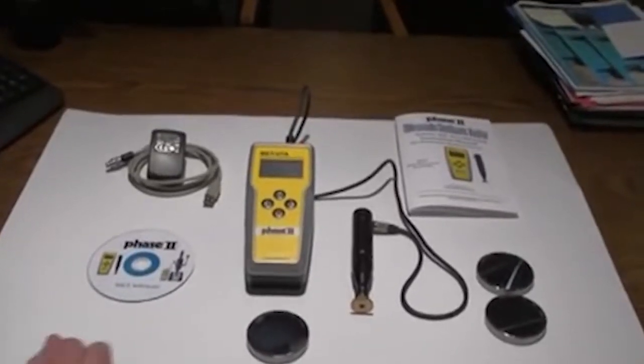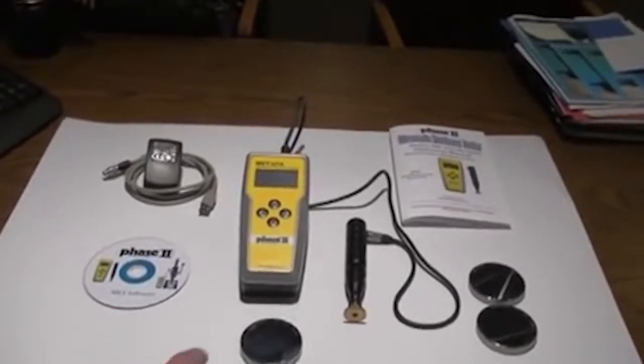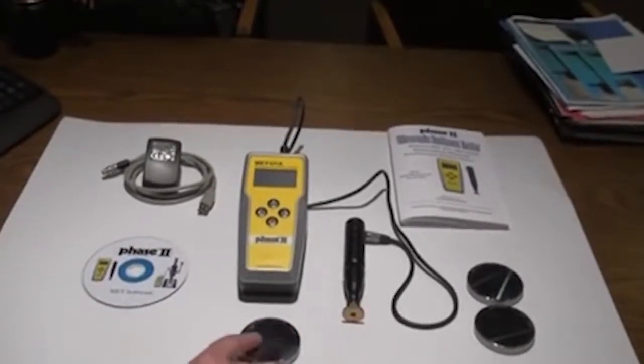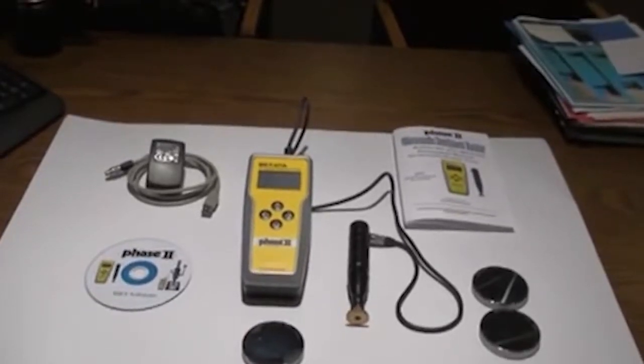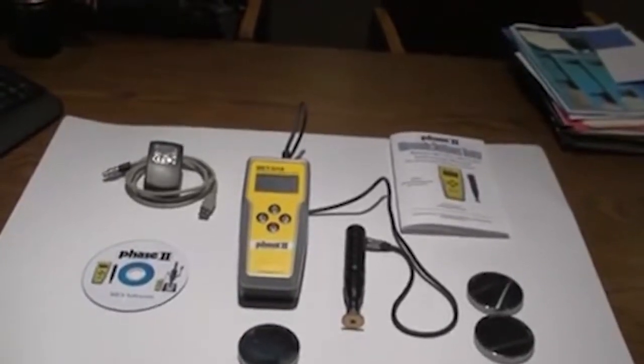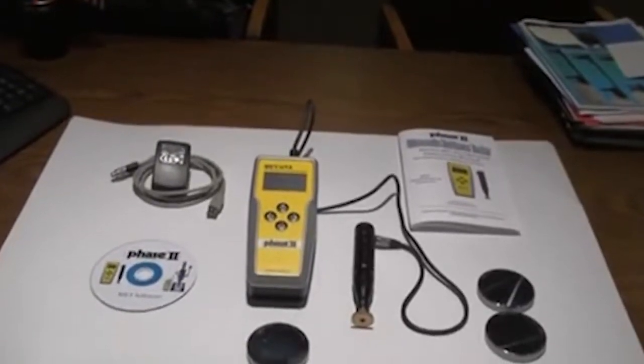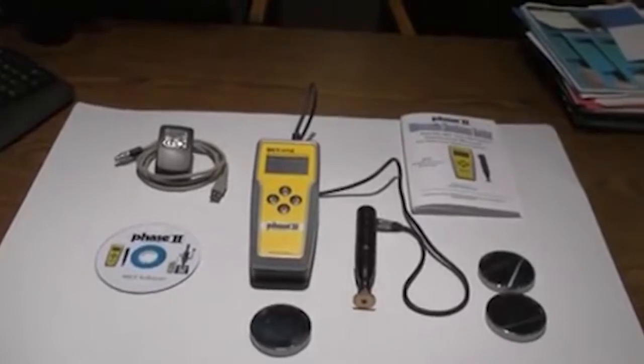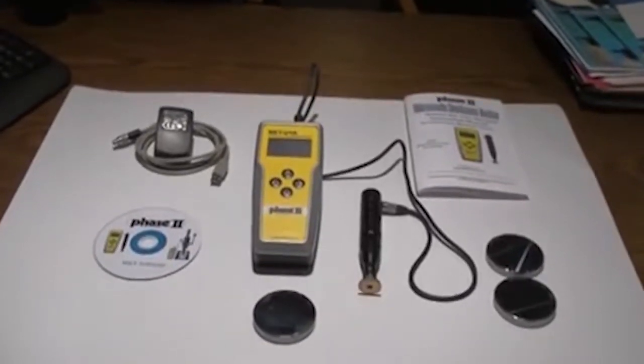The next parameter is surface roughness. If you are testing precision machine parts with a surface finish of better than 100 micro inches or 2.5 microns, then you can use the 1.5 kilogram load probe for most of your applications. For those surfaces which are rougher, the 5 kilogram load has an approximate maximum of 4 microns or 160 micro inches.